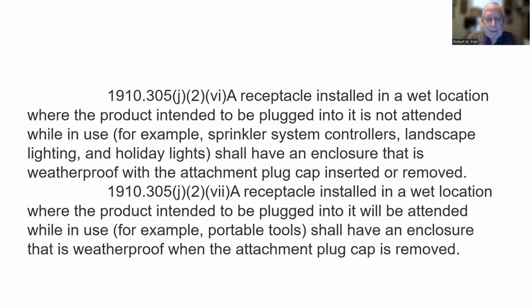Plant manager. All right. A receptacle installed in a wet location where the product intended to be plugged into it is not attended when in use, for example, sprinkler system controllers, landscape lighting, and holiday lights, shall have an enclosure that is weatherproof with the attachment plug cap inserted or removed. A receptacle installed in a wet location where the product intended to be plugged into it will be attended while in use, for example, portable tools, shall have an enclosure that is weatherproof when the attachment plug cap is removed.